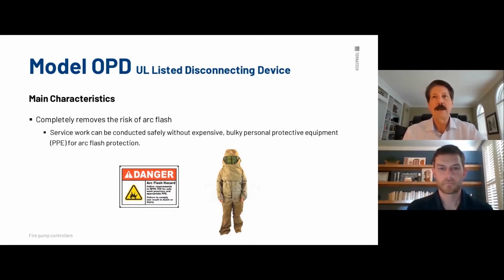And any good electrician will have a label on the front of the controller itself, and it will say, please do not open, arc flash potential, contact us. Or if it could be an industrial facility or university or what have you, and you get into OSHA requirements, well, these are going to follow to the letter of the law. And in these cases, you need PPE, exactly what we're showing here, personal protective equipment, before you open the door. And you need to know what level of PPE you need. And that's pretty much done with a coordination study for the whole system to determine at that point what the fault capability is if you were to have an arc flash or a fault, either phase to ground or phase to phase. So the cost of an OPD could be equal or less than having to buy PPE equipment for 1 or more people. That's huge. Literally, turn the OPD off, lock it out, go over, open your fire pump controller, and you could work on it in a short sleeve shirt or t-shirt.